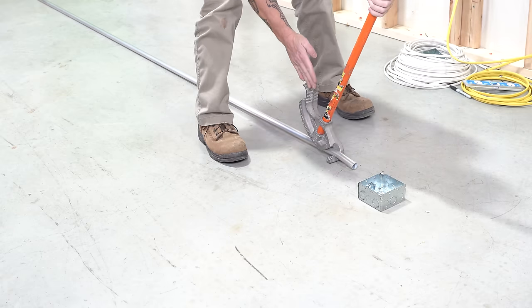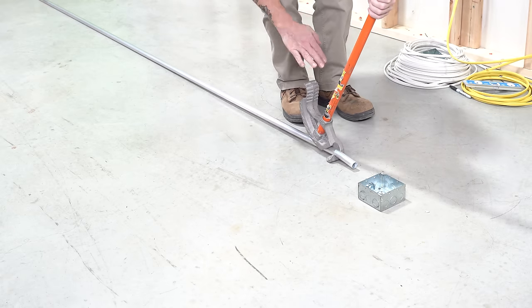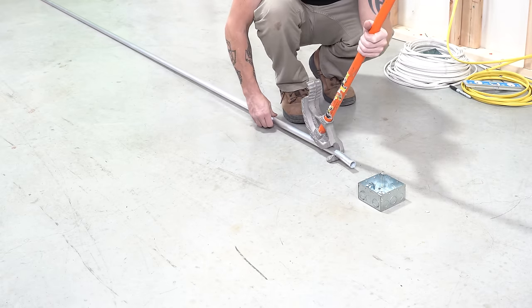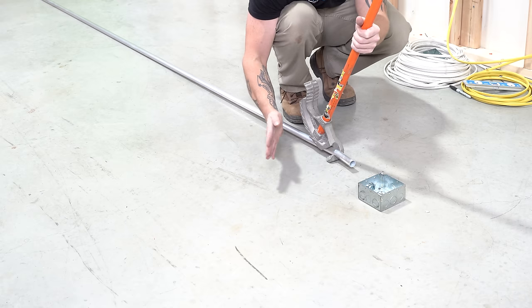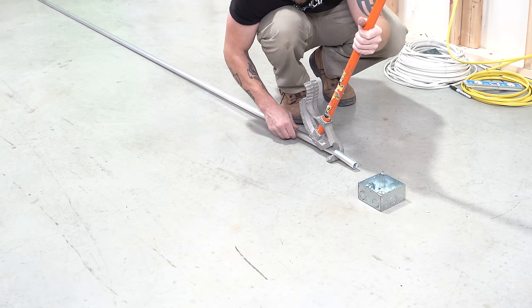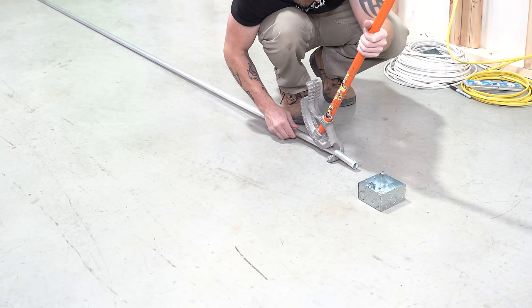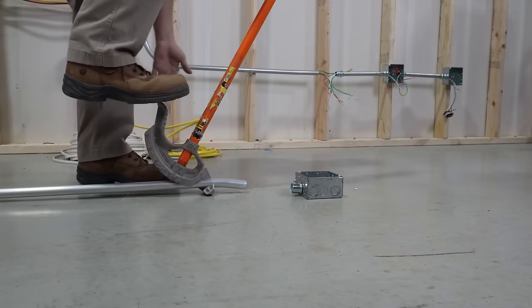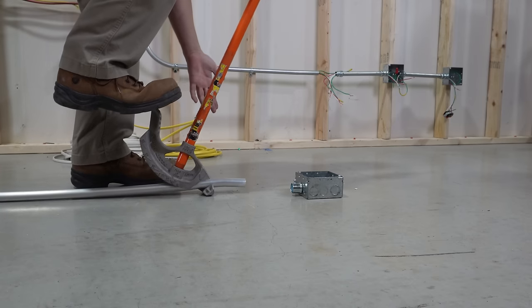And then again, you want to make sure that your conduit is straight. You don't want this thing to be turned so that your pipe's going off to the side. It's going to dogleg the crap out of it. So you want to make sure that everything is nice and straight. Same thing. We're going to bend down, barely kick it.